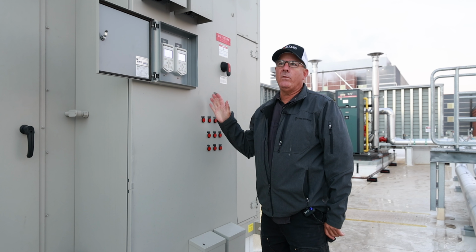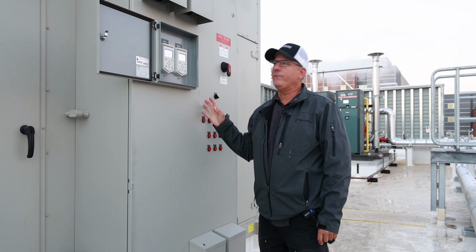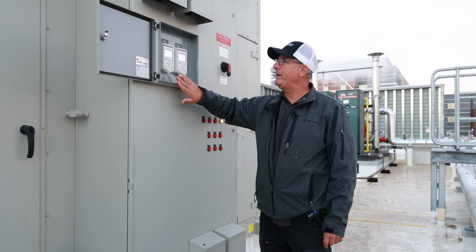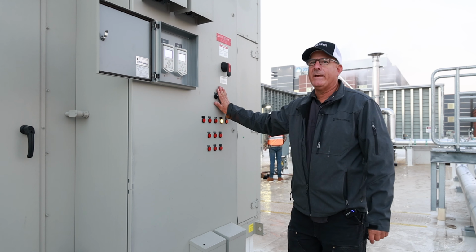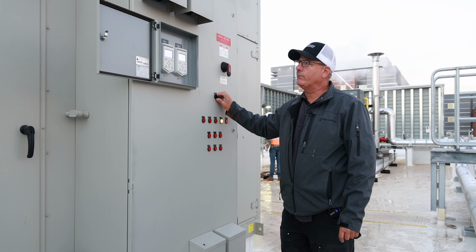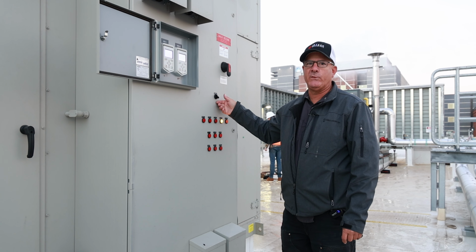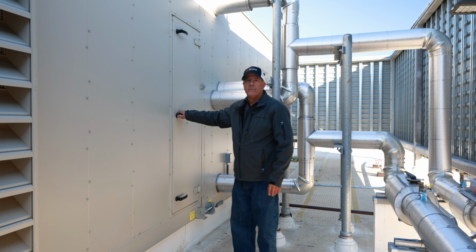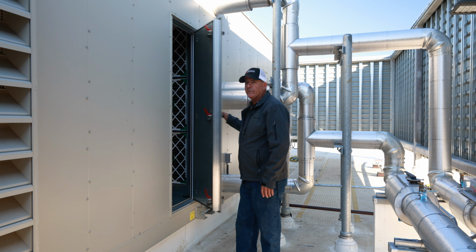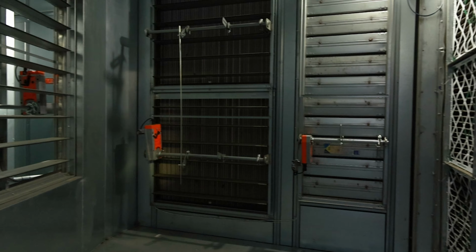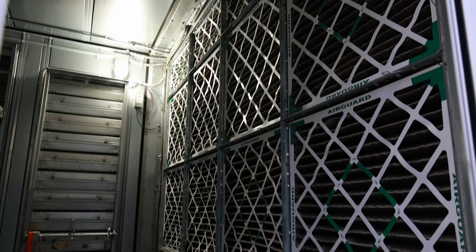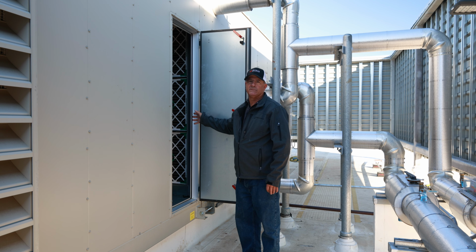Each fan wall for return and supply fans has 2 VFDs. Right here is the switch from VFD1 to VFD2 and your disconnect. Backside of the unit, we have the filter access, all pleated filters. This filter bank does have the ability to take pre-filters.